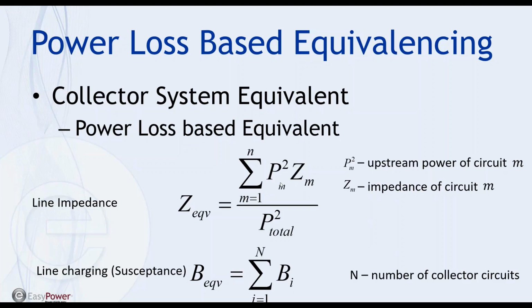And if we look at the final equation derived from that principle, you can see that the equivalized collector system impedance is just a weighted average of each collector circuit. Suppose here, for circuit M, you have upstream power flowing through this circuit, from your radial connection. The impedance of the circuit is Zm. So the total loss can be represented by the sum product of P squared and Z. If you divide that by the total power flowing through the equivalized circuit, that gives you the impedance. Hopefully, that's straightforward enough, and we will discuss the details in later slides.